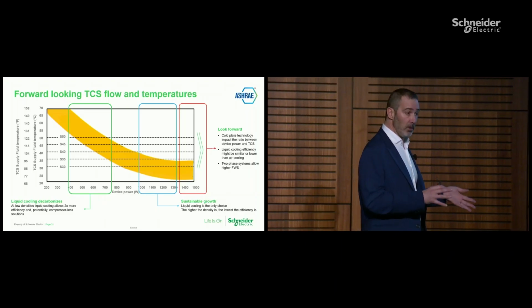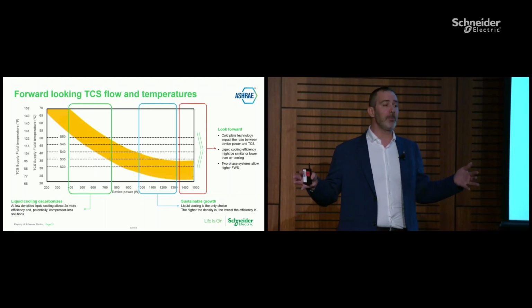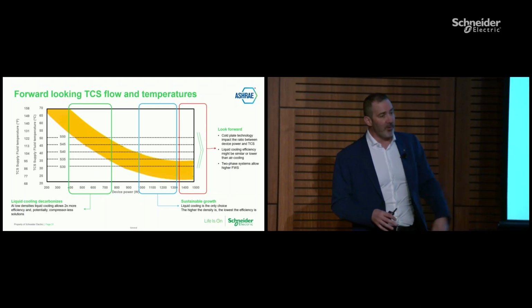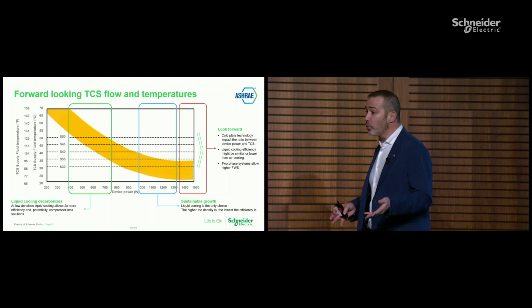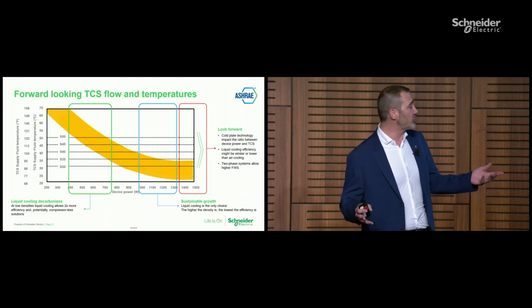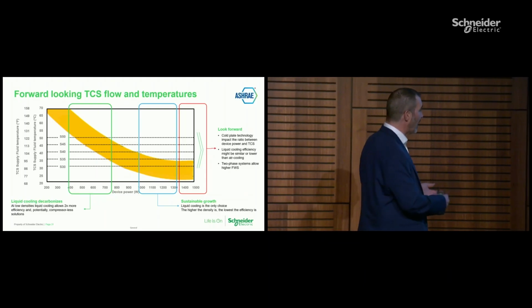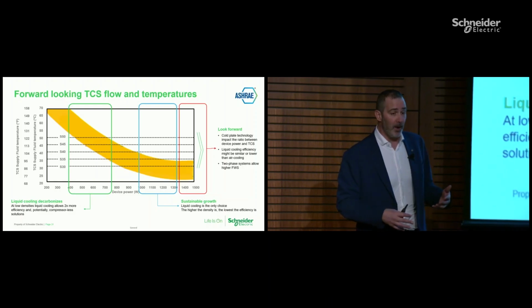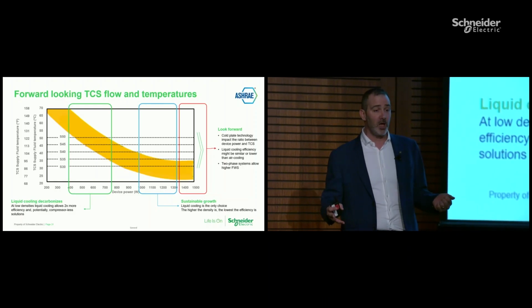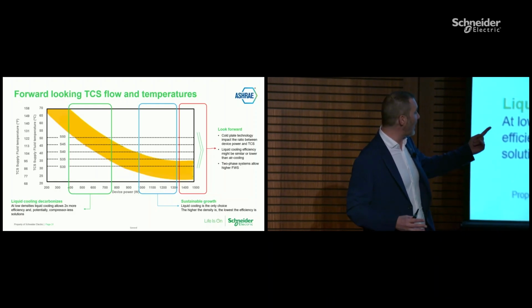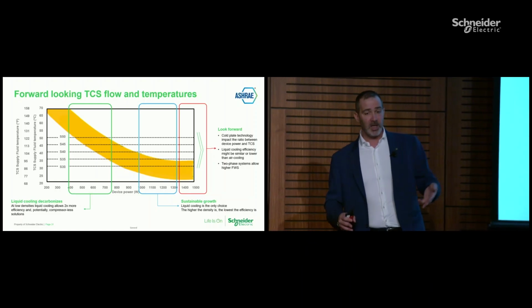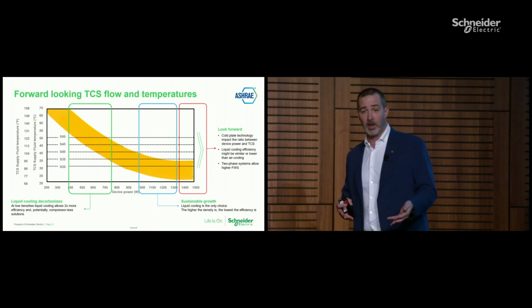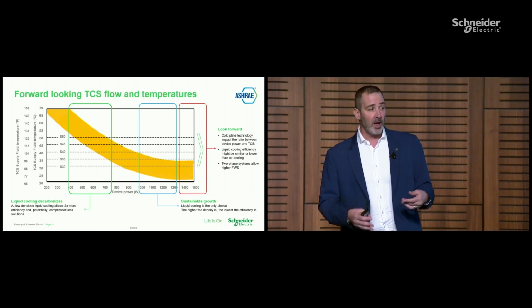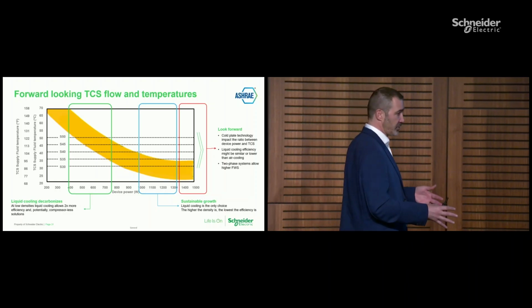Looking at this example, you can identify three major areas. The area where we have low density, similar to where we are today, around 400-500 watts per chip, meaning 15-20 kilowatts per rack, where the water temperature can be much warmer than what's used for air cooling today. So it's certainly a great way to decarbonize.